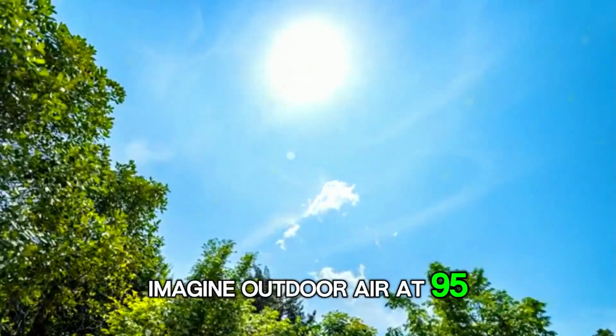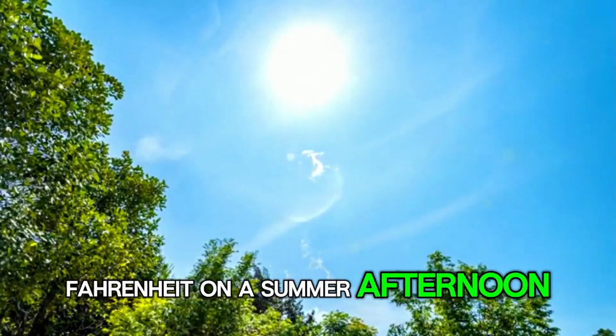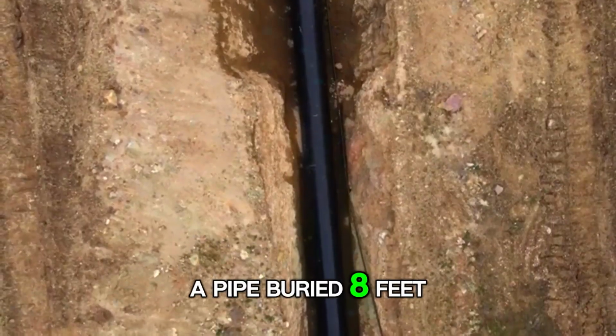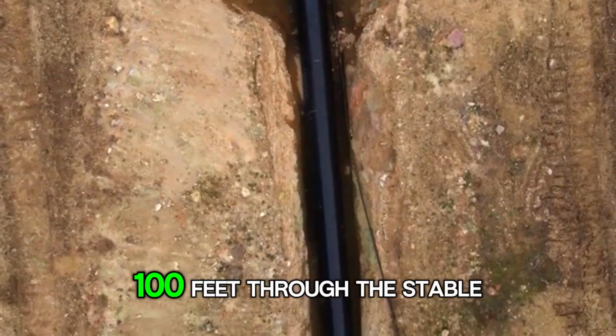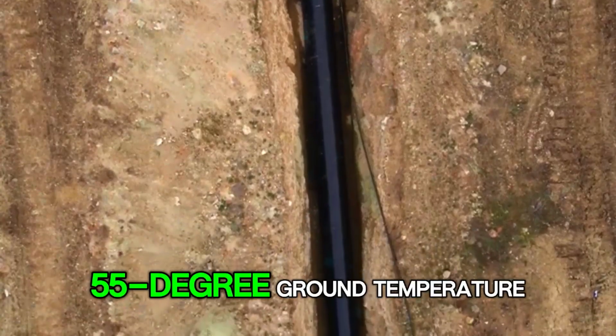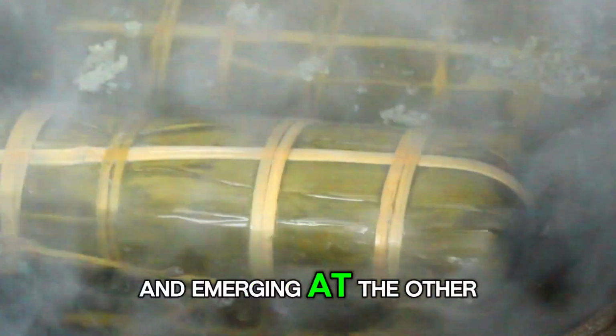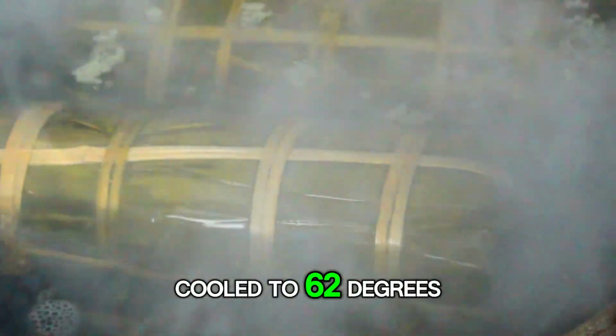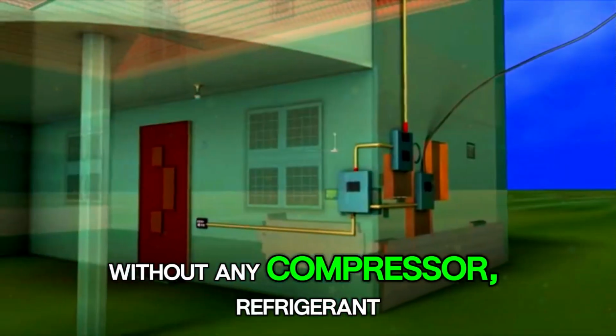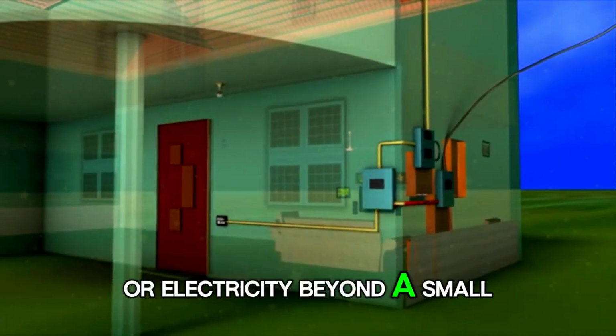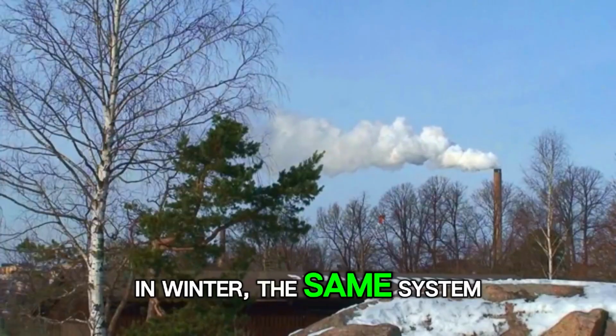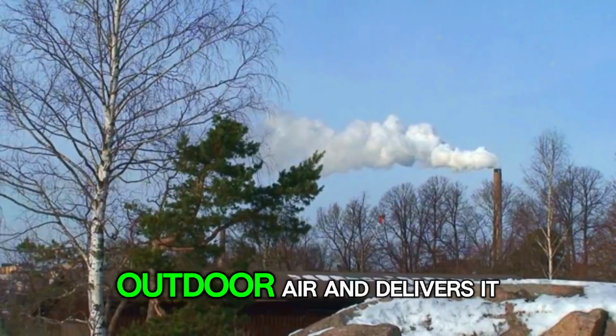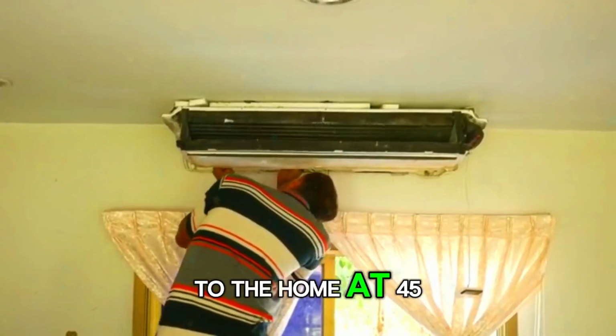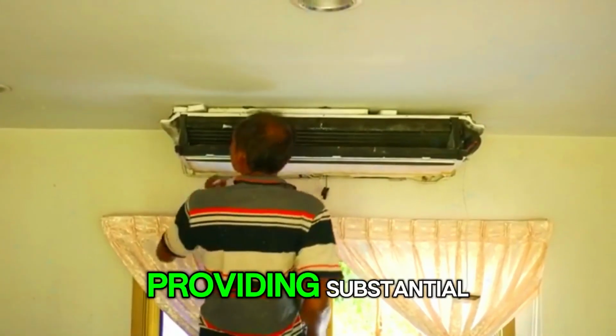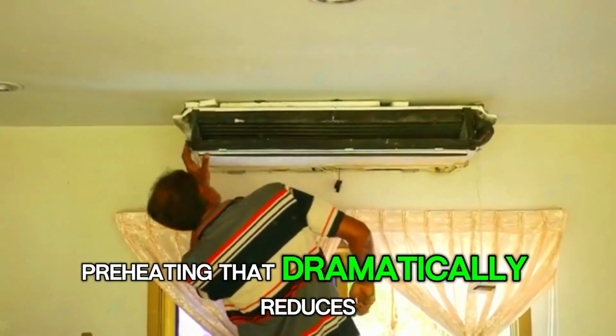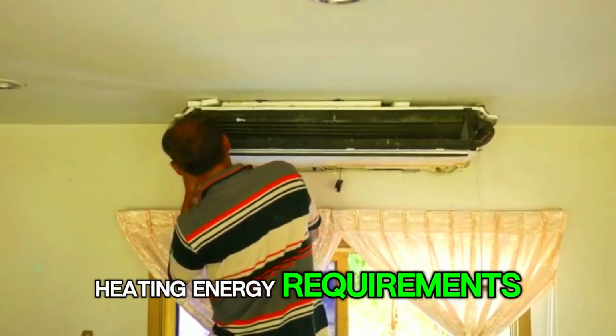Imagine outdoor air at 95 degrees Fahrenheit on a summer afternoon, entering a pipe buried 8 feet underground, traveling 100 feet through the stable 55-degree ground temperature, and emerging at the other end, cooled to 62 degrees, without any compressor, refrigerant, or electricity beyond a small fan. In winter, the same system takes 15-degree outdoor air and delivers it to the home at 45 degrees, providing substantial preheating that dramatically reduces heating energy requirements.